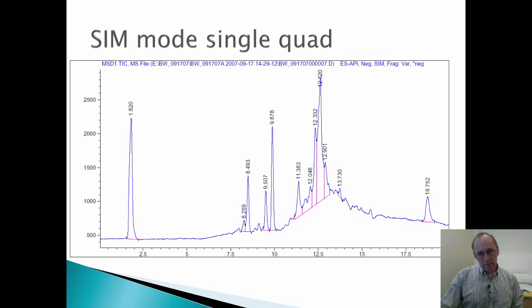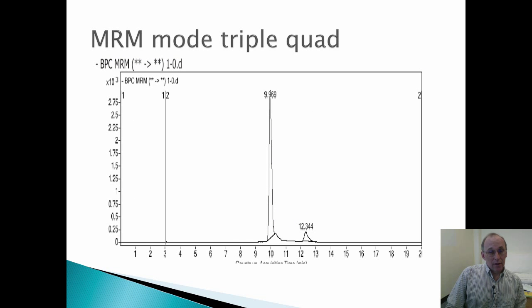Now, if we take the same sample, analyze it on a triple quad using MRM mode, this trace now looks like this. So all the compounds that have the same parent M over Z value but not the same product M over Z value are filtered out. This gives us a nice, clean peak, which we can much more confidently quantitate and get a good, accurate number on.